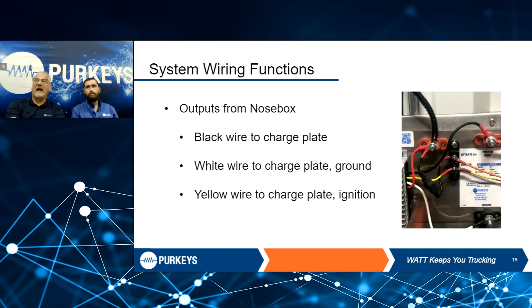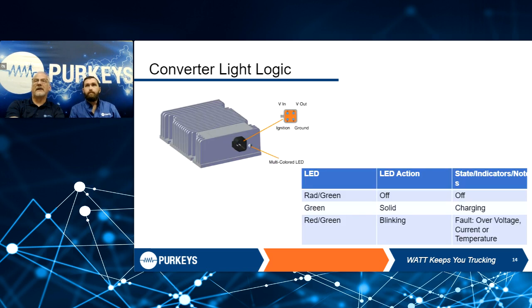Then the outputs: the black wire, which goes to the input on the charge plate, the white, because we ground our system separately, and then the yellow. The yellow tells our DC-DC converter to start charging, and the voltage on that wire should be at least 10 volts. Your black and white should be similar to what you see on the input blue and white, so if I see 13.2 coming in, I should be within a volt or so down here, usually less.